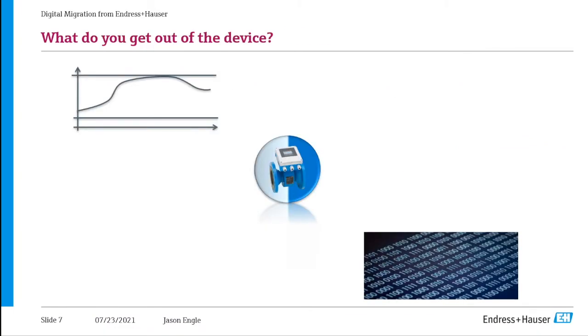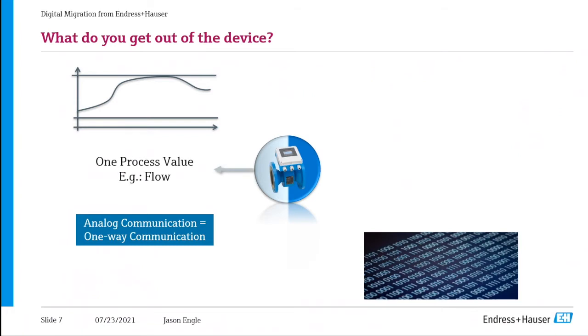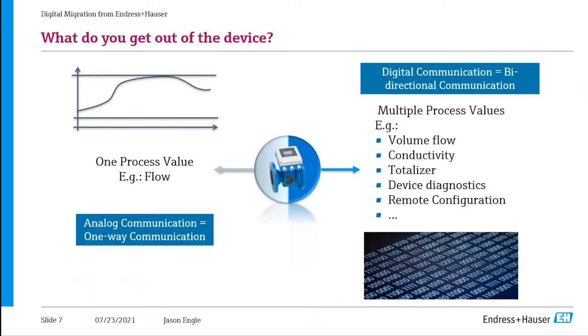Why is that important? Take a magnetic flow meter in the analog world — you get the flow output, a 4 to 20 milliamp signal scalable to, say, 0 to 100 gallons. Compare that to the digital side, where you can get so much more: flow, conductivity, a totalizer, device diagnostics, remote configuration — all part of that two-way communication. The value of the device grows significantly on the digital side because there's so much more information that can be taken from the field device to bring further value.